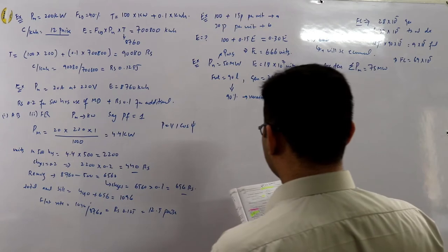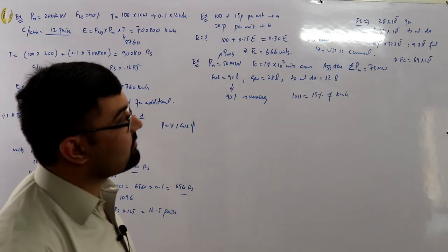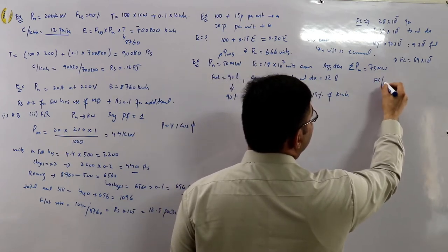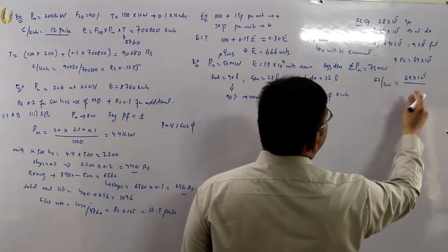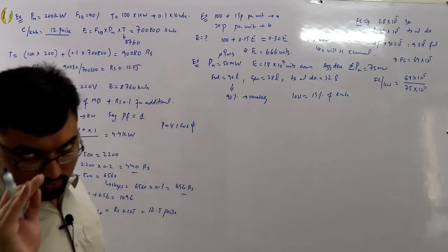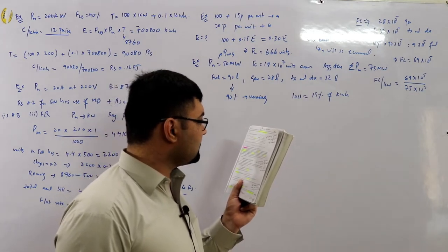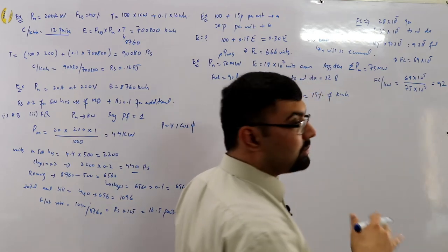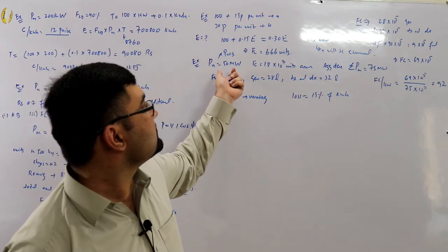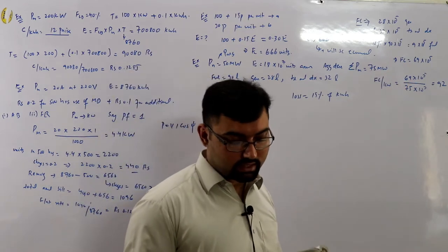This cost is spread over the aggregate maximum demand of all consumers (75 megawatts). Fixed charges per kilowatt = 69 lakhs / 75,000 = rupees 92. The diversity among consumers reduces the fixed cost per kilowatt — without diversity, this cost would be higher.